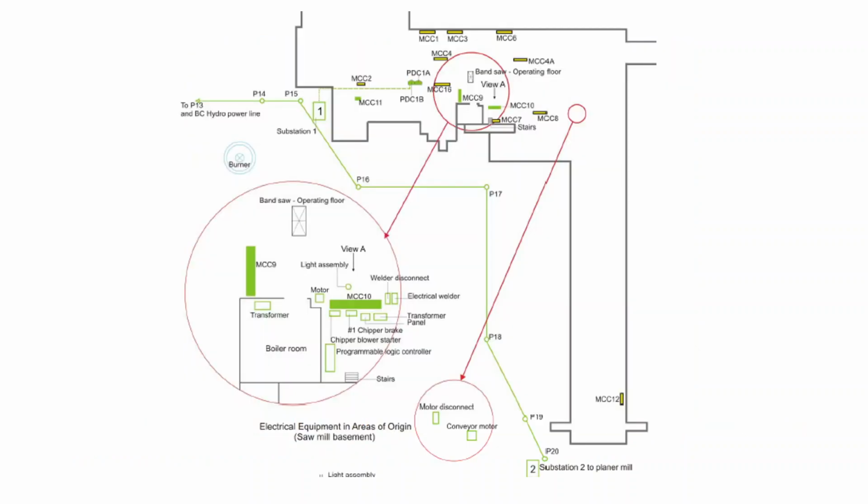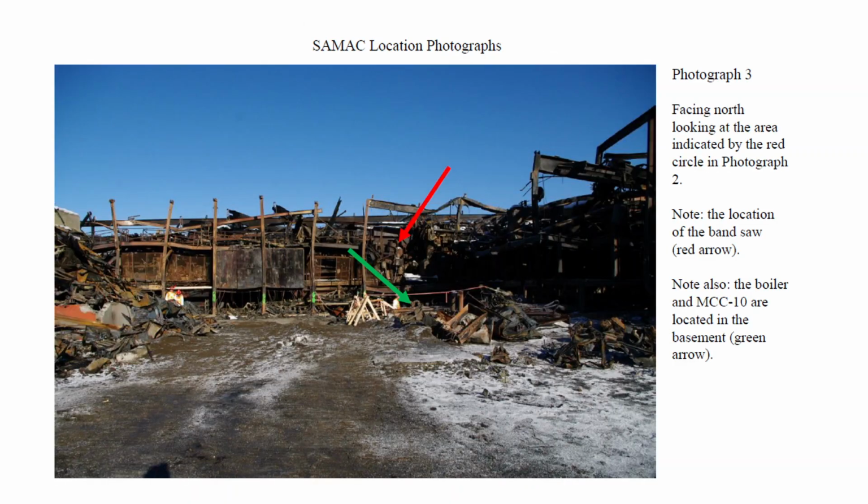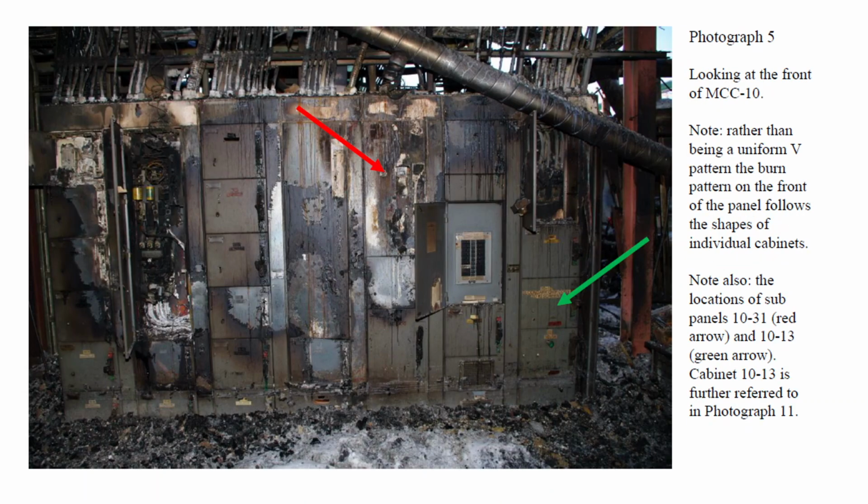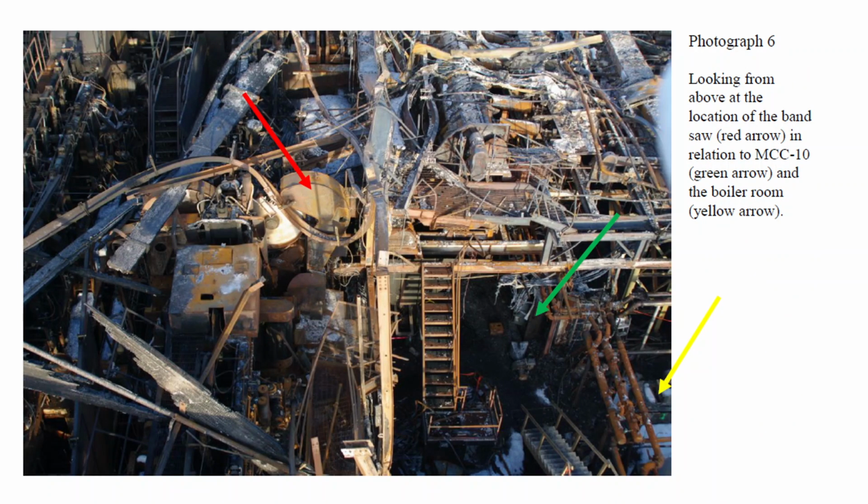What we can see from the technical safety report that was made after the explosion is that they centered where the explosion likely came from, and it was an MCC room. You can see the scale of destruction that took place throughout the facility. It was determined that this MCC room here was the initial location of the explosion, and the room itself was torn to bits.